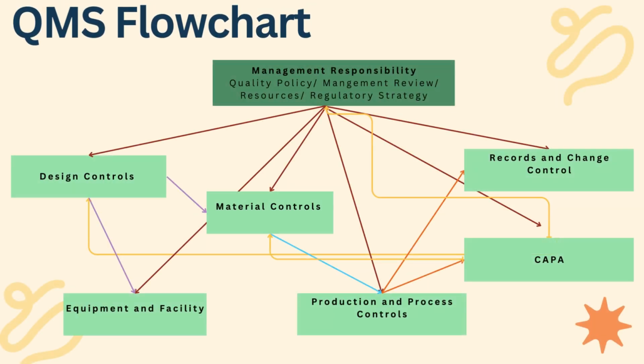So now we're going to look at our QMS flowchart and how all of these design controls interact with each other. Obviously, management responsibility covers all of these controls. They allocate resources, conduct management reviews, and establish overall regulatory strategy, including planning. Design controls ensure that the stent is developed systematically from user needs through verification and validation. This includes defining intended use, translating requirements into design inputs and outputs, and verifying performance. Design outputs feed directly into material selection, equipment requirements, and production processes.